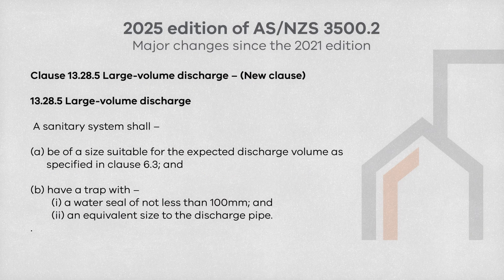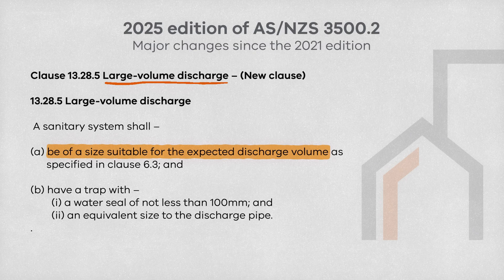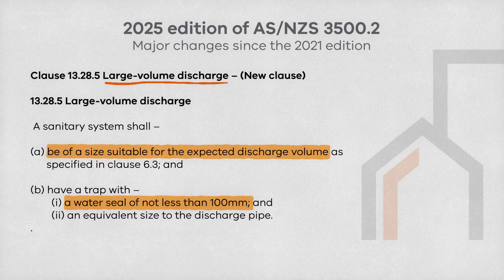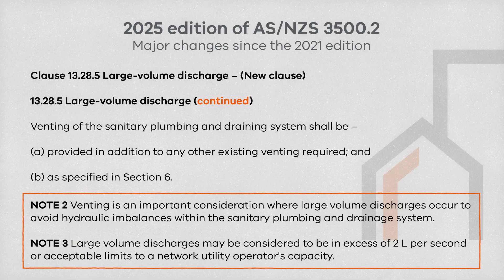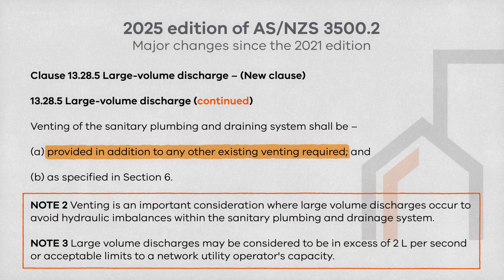There are also new requirements regarding large volume discharge. This clause states that the sanitary system must be appropriately sized for the expected discharge volume and include a trap with a water seal of at least 100mm matching the size of the discharge pipe. It is also a requirement that venting must be provided for the sanitary drain in addition to any other existing venting requirements, as specified in section 6 of the standard.